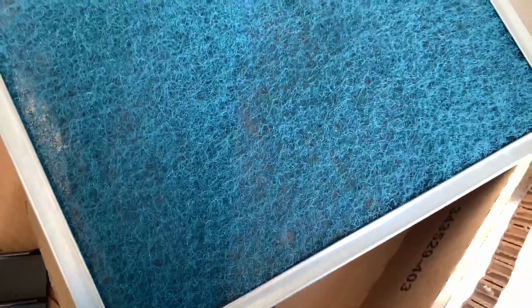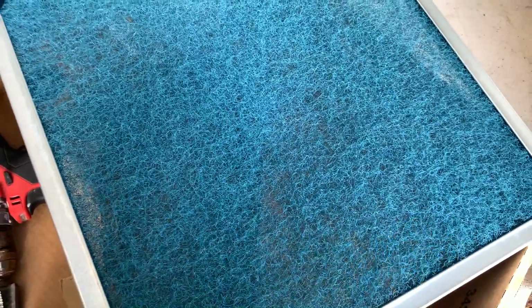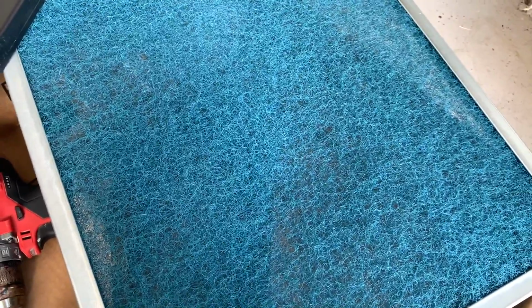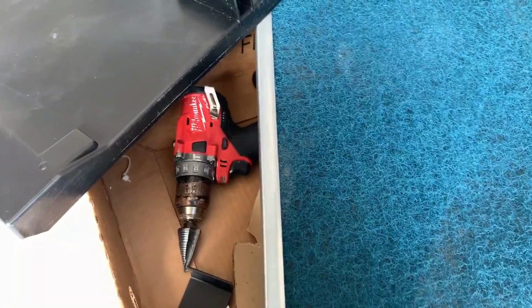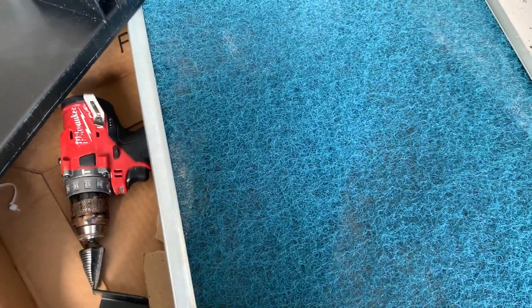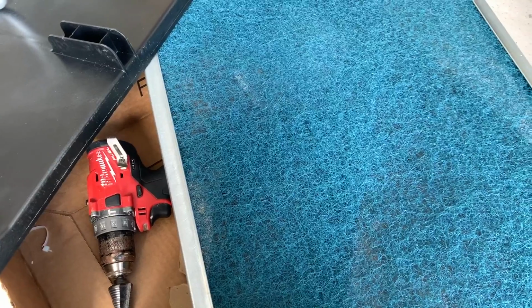Leaving these hog hair filters as the primary filter, I would suggest not doing that. Use 4-inch media, special, like the Infinity Air Purifier or something like that, or filter back returns. In this case, we're going to put the 3-inch Honeywell filters in the filter back returns, so that way you've got the larger media, but still utilizing the filter back.